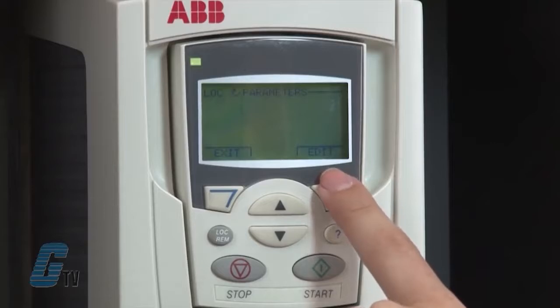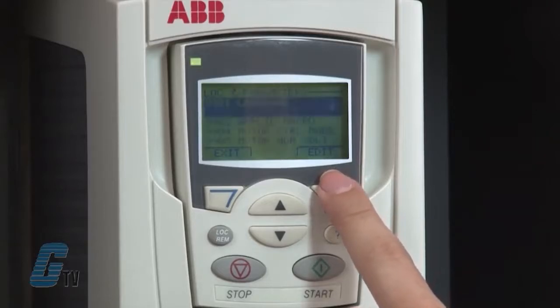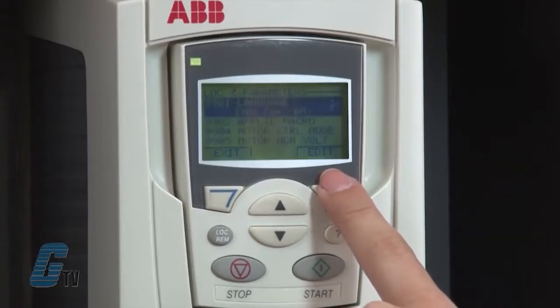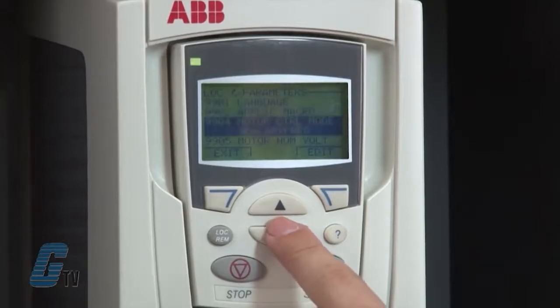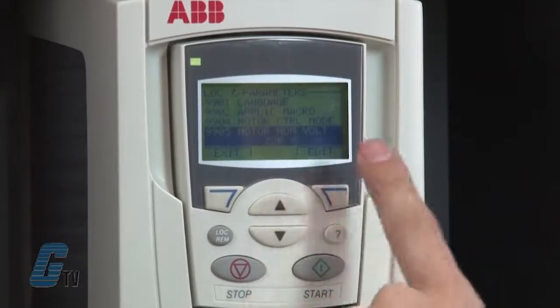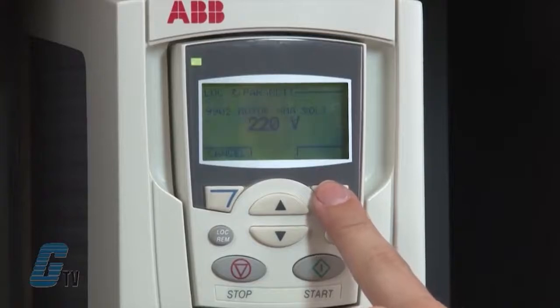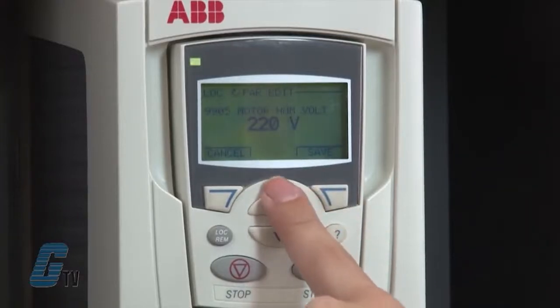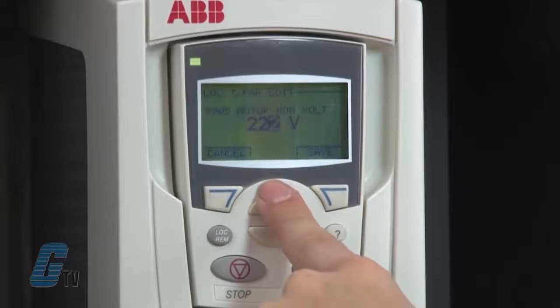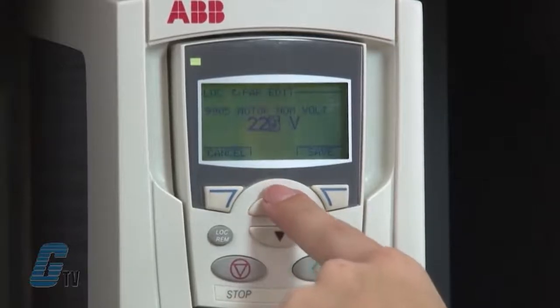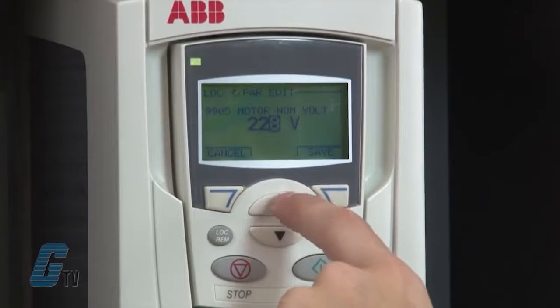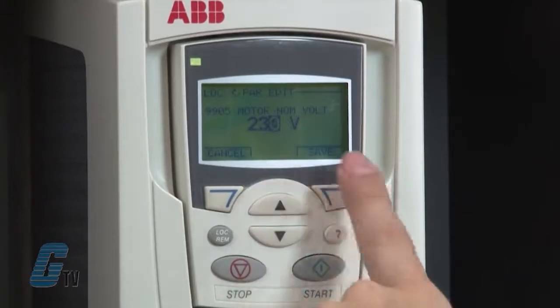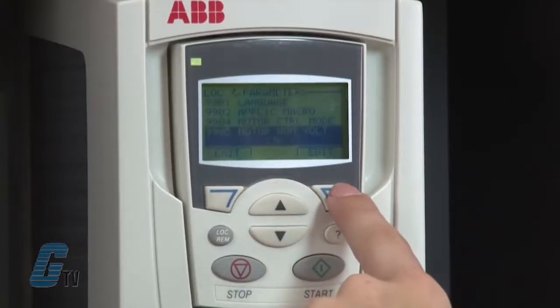I am now into the group 99 startup data parameter list. Since I want to enter the motor data, I will arrow down to parameter 9905, motor nominal voltage, and push the edit button. Using the up and down arrows, I will enter the voltage of the motor from the nameplate. The motor in this demonstration unit is 230 volts. After I have set the voltage, I will push the save button.